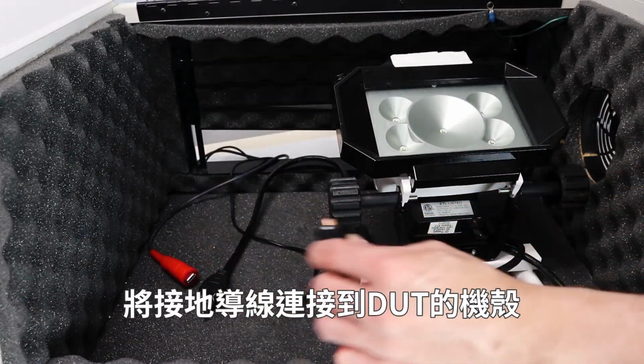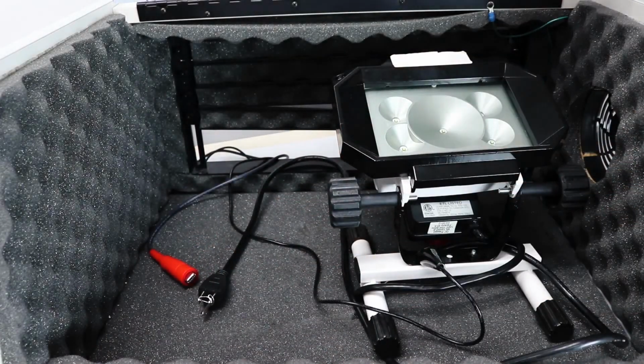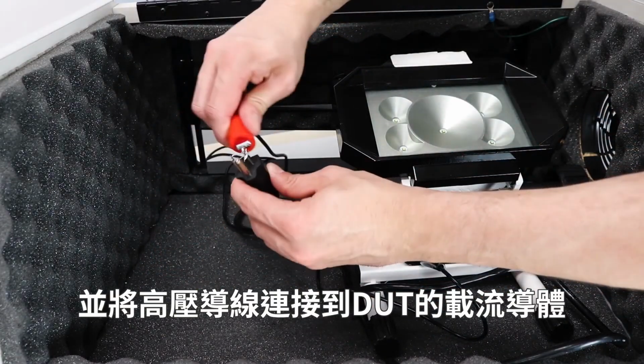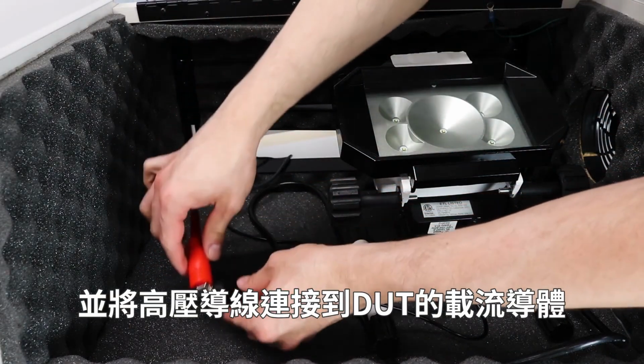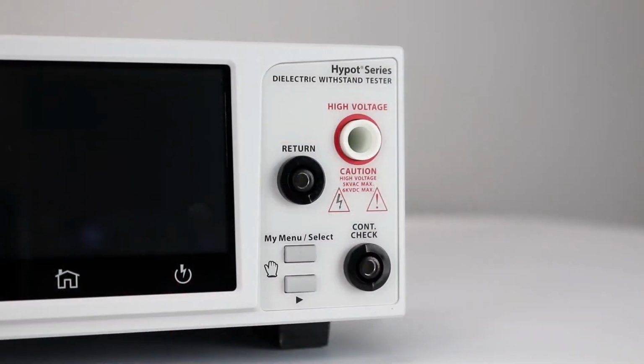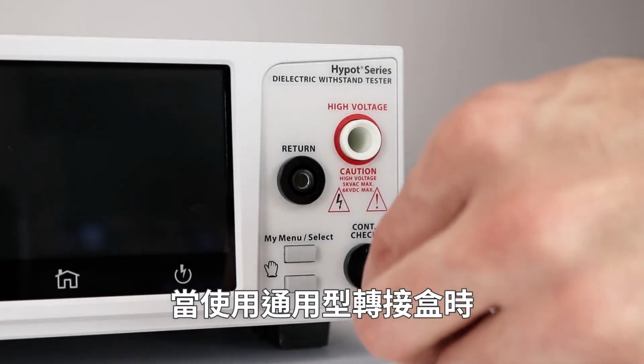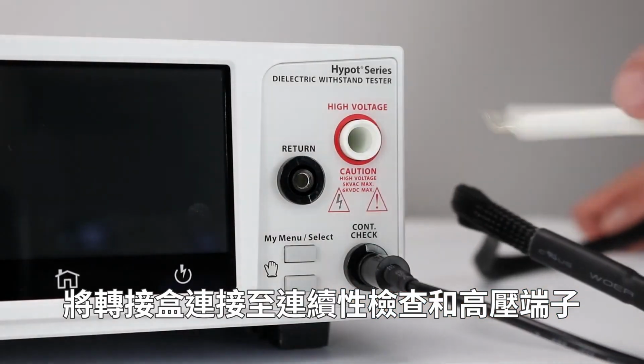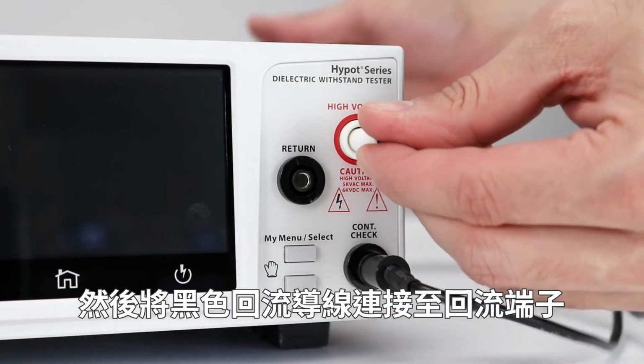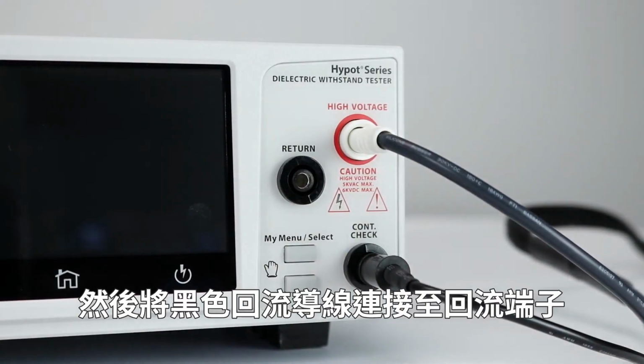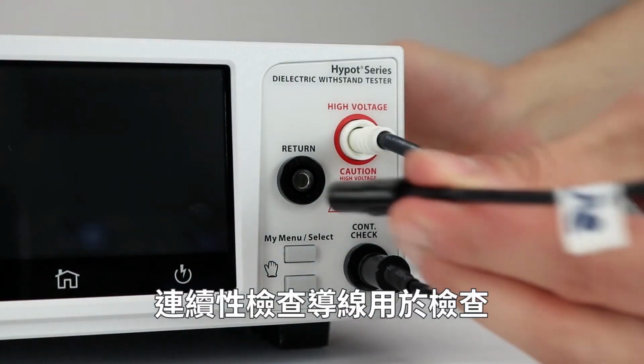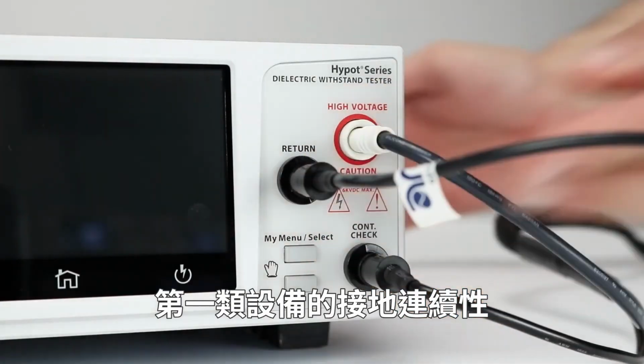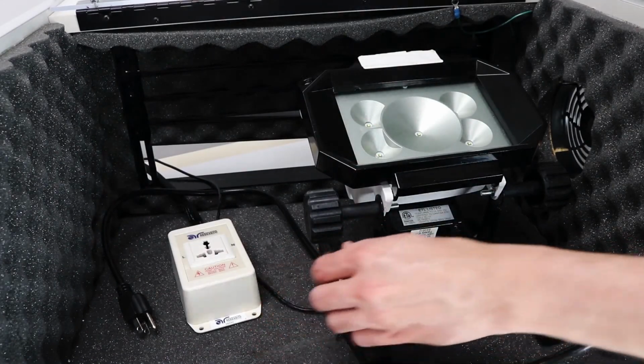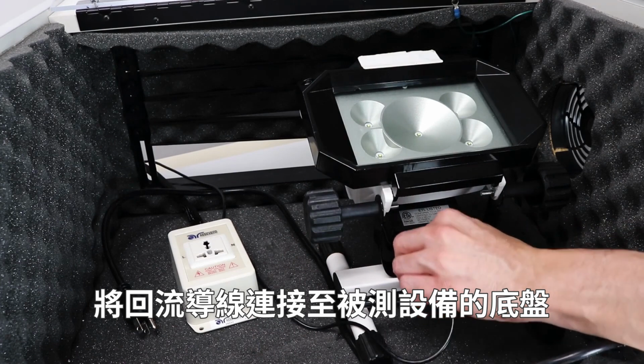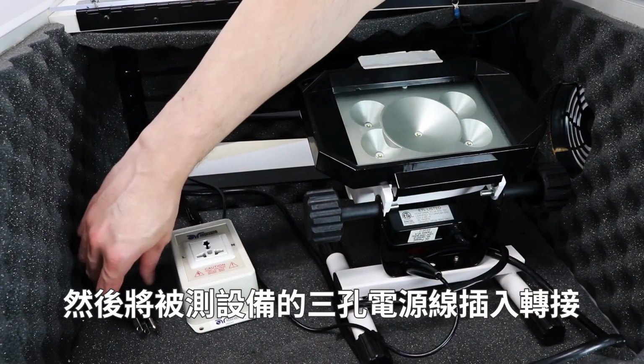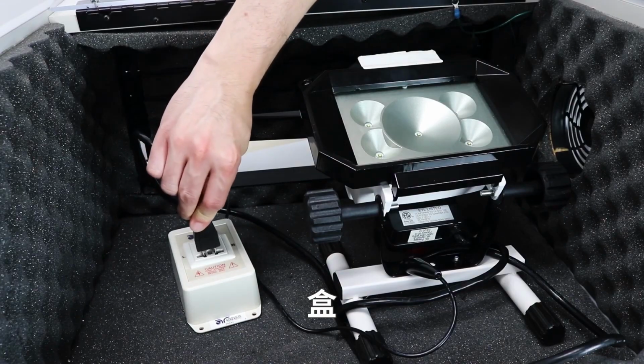Connect the return lead to the chassis of the DUT and connect the high voltage lead to the current carrying conductors of the DUT. When using the universal style adapter box, connect the adapter box to the continuity check and high voltage terminals. Then connect the black return lead to the return terminal. The continuity check lead is used to check for ground continuity for a Class 1 device. Connect the return lead to the chassis of the DUT, then plug the 3-prong cord of the DUT into the adapter box.